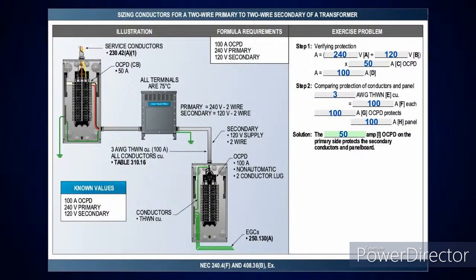Well, how do I know this is correct? Well, if I take 240 volts, divide it by 120, and then multiply that by 50 amps, it gives you 100 amps. So therefore, in order to protect those conductors and panel from that transformer, I would need number 3 conductors that will protect for the 100 amp overcurrent device. And the 50 amp overcurrent protection device on the primary side is protecting the secondary conductors and panel boards on that secondary side. Okay? And that's just proving what's there.